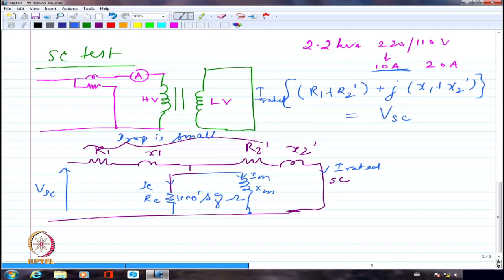So this VSC, what I apply, will normally be done through an auto transformer. So I'm going to show the auto transformer here. The voltage is applied with respect to only a fraction of the total turns available in the total auto transformer winding. So this is where I apply the 220 volts or 230 volts. I'm going to apply V rated probably at this point. Rated voltage is applied here, from there to a variac or auto transformer. From the auto transformer, this is the variable jockey point, which is going to probably be put at the very minimum number of turns. So I will slowly increase the voltage applied by increasing the jockey position of the transformer, or I have to rotate it, and make sure that I don't exceed the rated current.